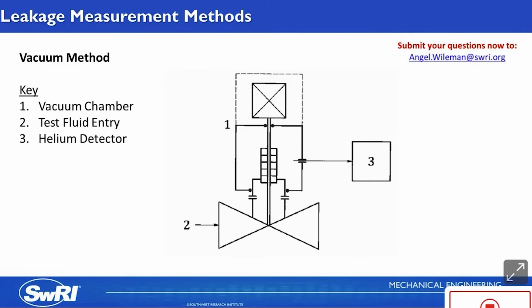Now that we've discussed the maximum acceptable external leakage to qualify the valves, let's discuss the different methods for measuring external leakage. ISO 15848-1 accepts two methods for measuring the stem seal leakage, the vacuum method and the accumulation method. The vacuum method is shown in this schematic, and it's used with helium gas only and a helium mass spectrometer to measure leakage. Using this method, the leakage source, which includes the body bonnet joint and the stem seal, is enclosed in a tight chamber. The chamber is evacuated and connected to the mass spectrometer, and it must be tight enough to pull a vacuum on the volume, which promotes accurate leakage measurement.